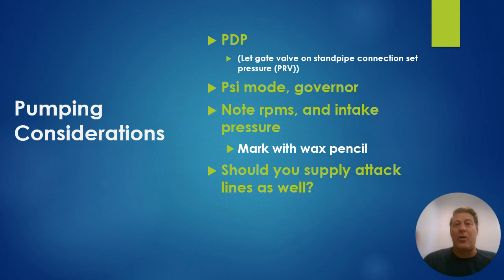We have 1,500 GPM pumpers in our fire department, and they typically range somewhere just a little more, a little less than that, or around 1,500 on virtually any pumper. So sure, it should be pretty easy to pump an additional hand line or two on top of that. That's what we would do on a normal fire anyway. But it goes back to department preference, but I feel like smaller FDCs, absolutely, we can stretch some lines off of it. No need to pull a whole other apparatus into pumping smaller flows. Larger flows, we would probably want to separate those functions.